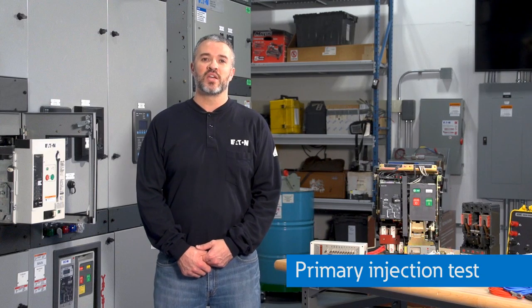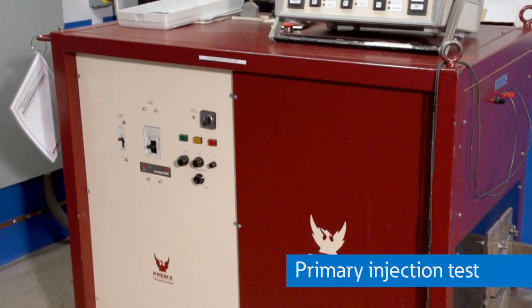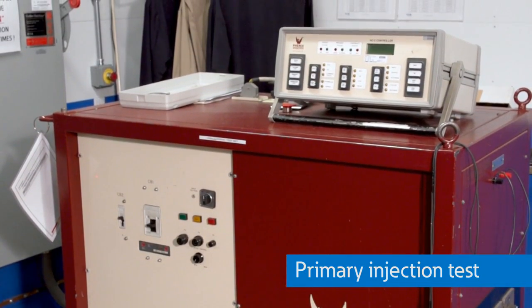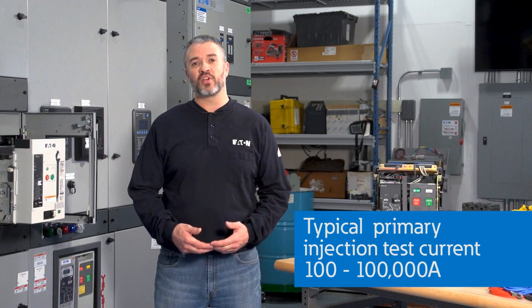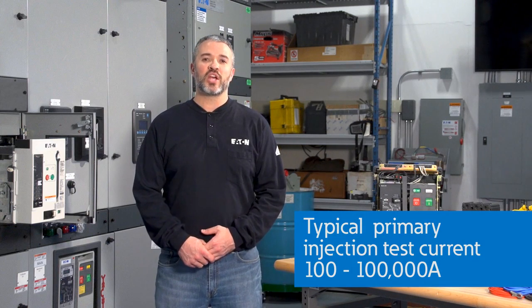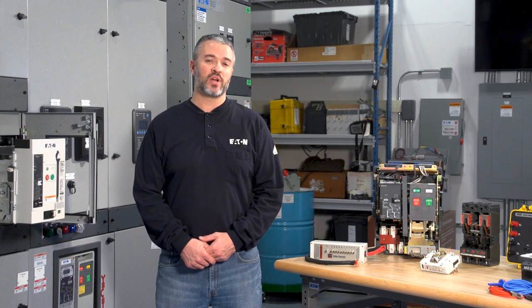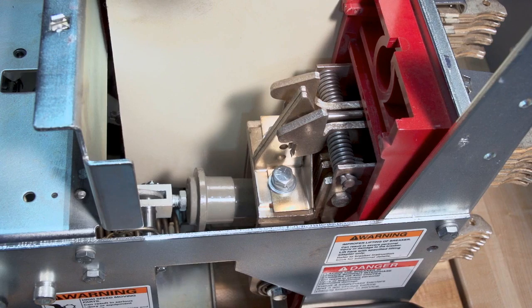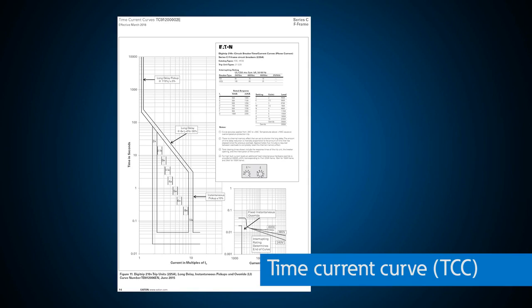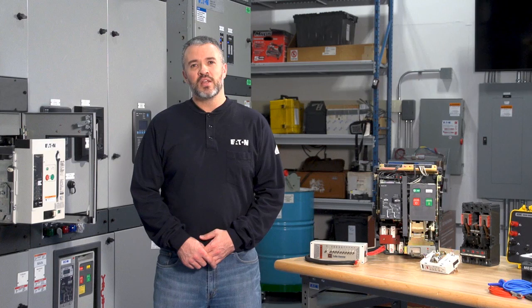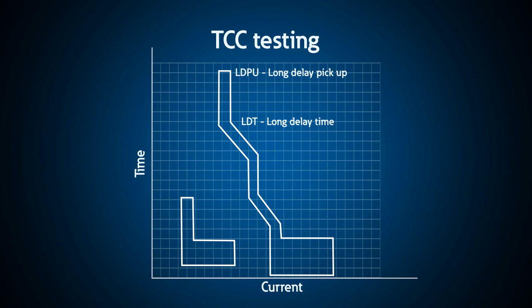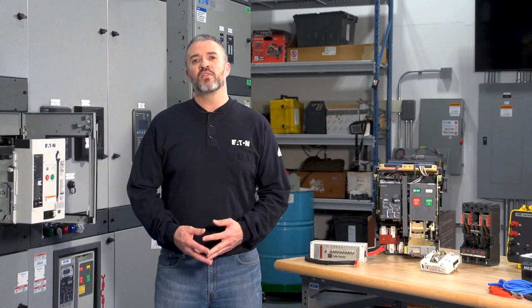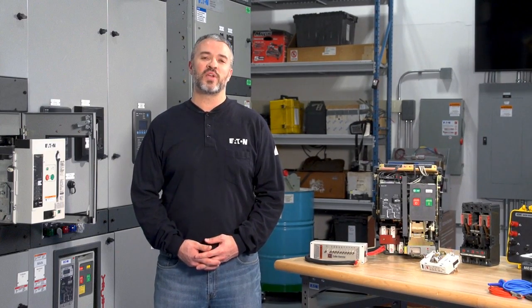A primary injection test is done by connecting a circuit breaker to a high current test set using the primary contacts. This is a much more reliable test because it pushes a large amount of current through the entire breaker. Primary injection will not only test the trip unit and direct trip actuator, but also the current sensors and opening of the circuit breaker's contacts. There is a certain range of acceptable tolerances for a circuit breaker to pass this test given a fixed amount of current versus time compared to a particular time current curve, or TCC. Testing would typically include evaluation of long time pickup and delay, short time pickup and delay, instantaneous pickup, and ground fault settings. For arc flash reduction, maintenance mode settings should also be evaluated.